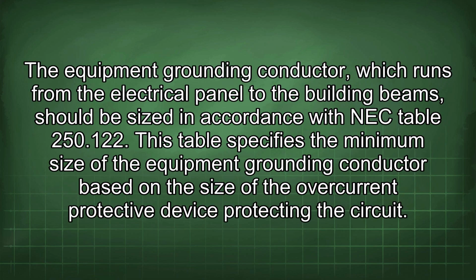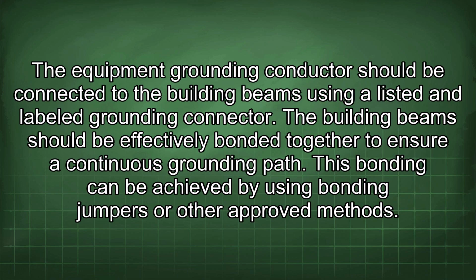The equipment grounding conductor, which runs from the electrical panel to the building beams, should be sized in accordance with NEC Table 250.122. This table specifies the minimum size of the equipment grounding conductor based on the size of the overcurrent protective device protecting the circuit. The equipment grounding conductor should be connected to the building beams using a listed and labeled grounding connector. The building beams should be effectively bonded together to ensure a continuous grounding path. This bonding can be achieved by using bonding jumpers or other approved methods.